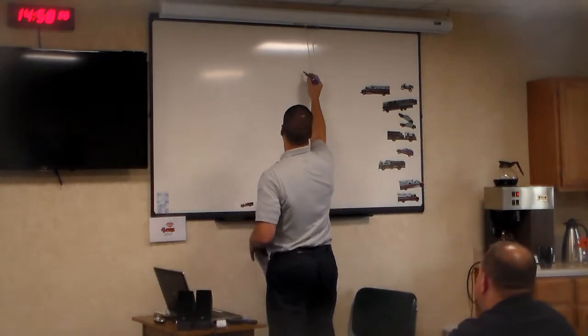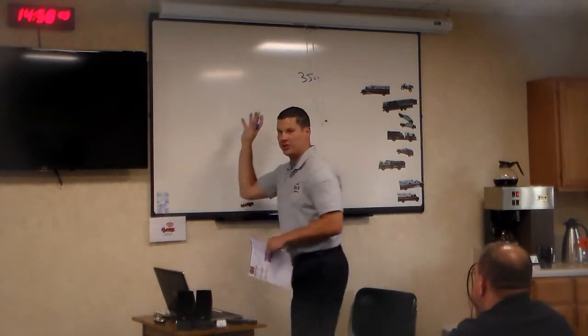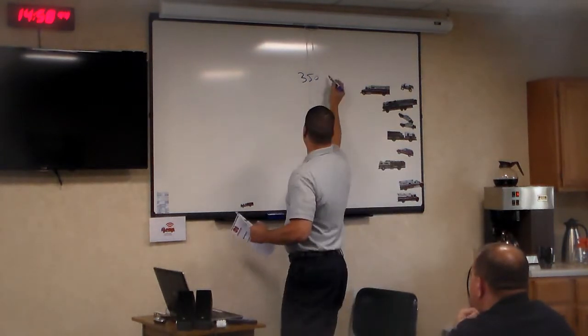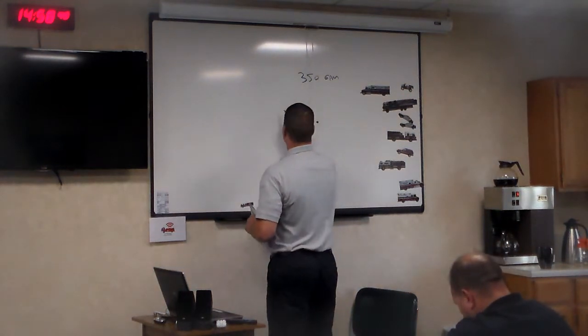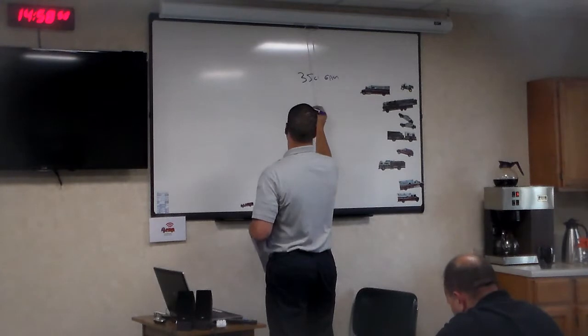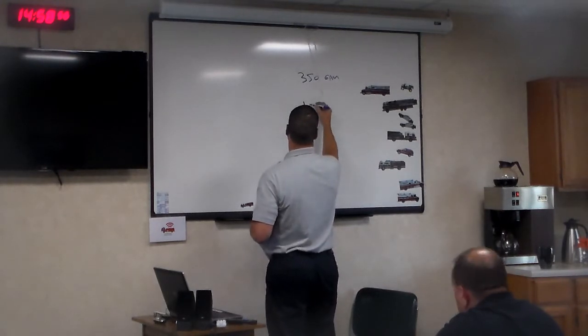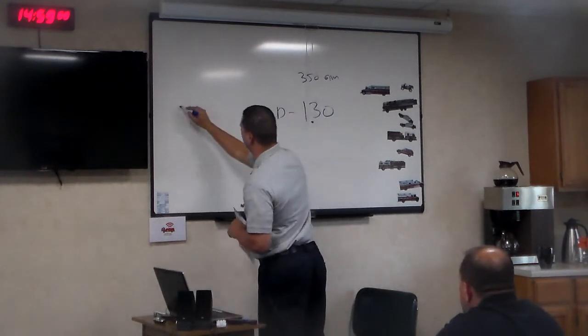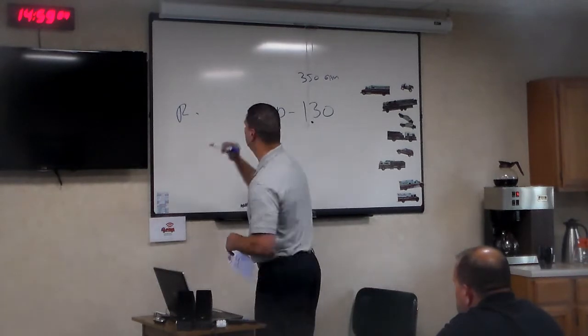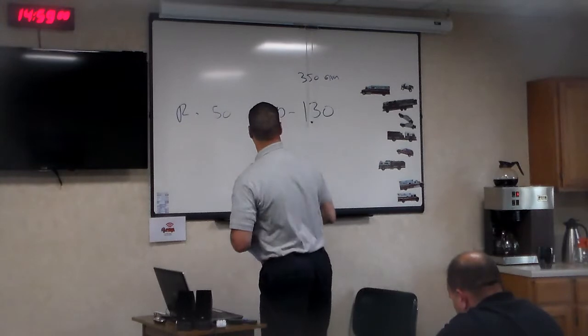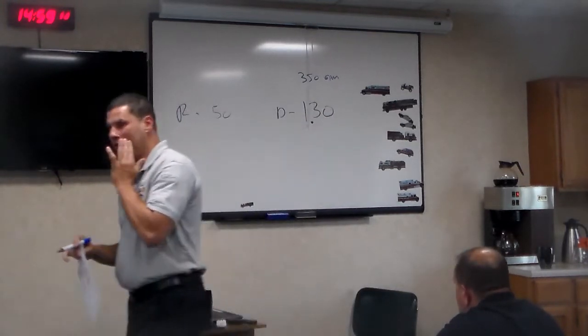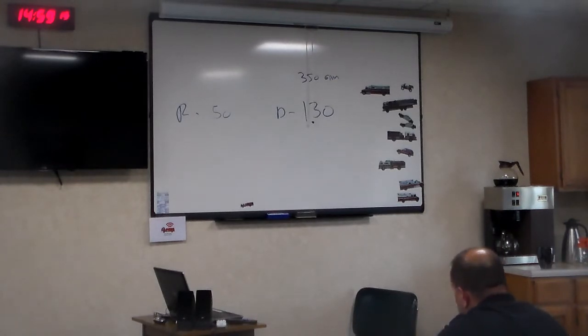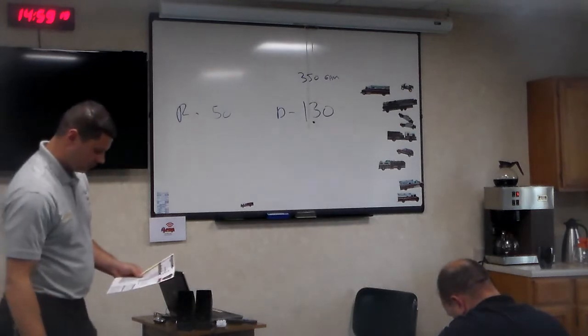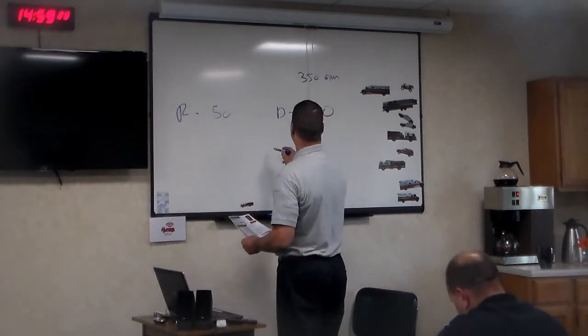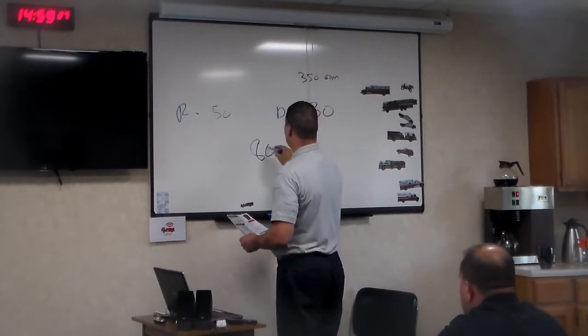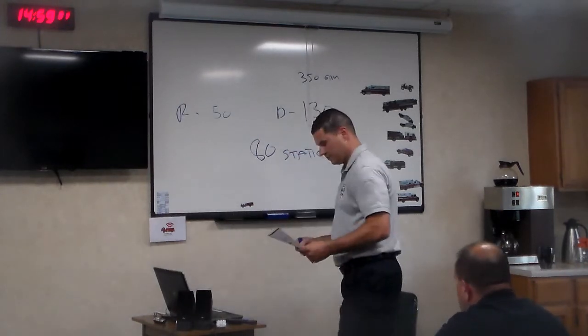Let's say you are flowing, it doesn't really matter specifically what you're flowing. Let's pretend that we're flowing 350 gallons of water, through whatever combination, 1 line, 2 lines, whatever it is. You're flowing 350 gallons per minute. Your discharge gauge is reading, let's say, 130. So that's your discharge gauge. Your residual, which is on what side? The left. Let's say that's reading 50. All right. Can you flow, or how much water is left in the hydrant? What's your static pressure initially? Static was 80.